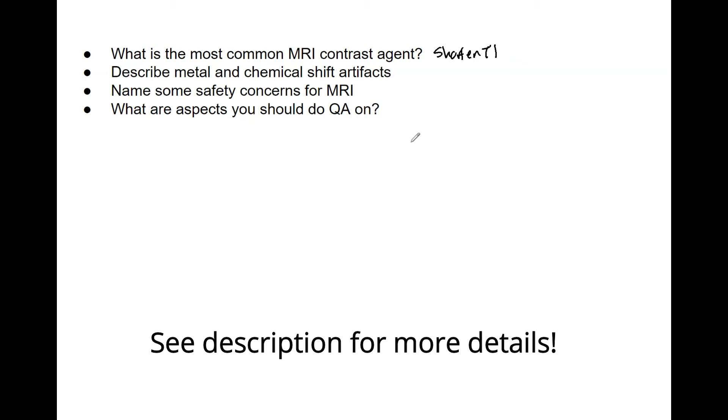What are aspects you should do QA on? First thing is spatial distortion. This is very important - you're banking on MRIs being exceedingly accurate, but with the slice thickness and the axial distance accuracy, you need to ensure there is no distortion because you may not be able to tell within the image itself, and that will lead to errors when treatment planning.